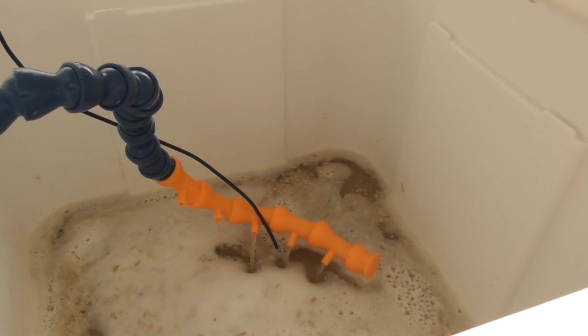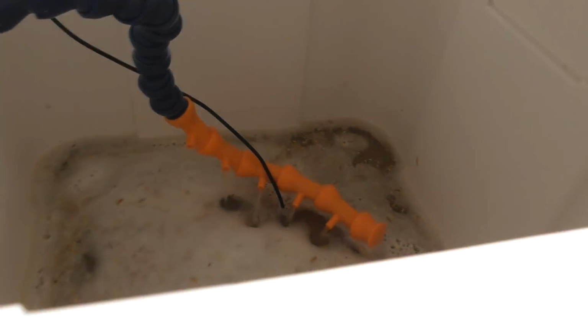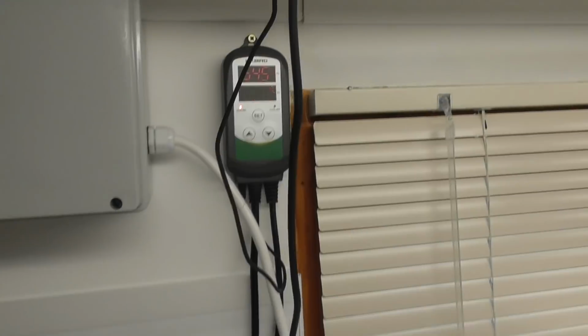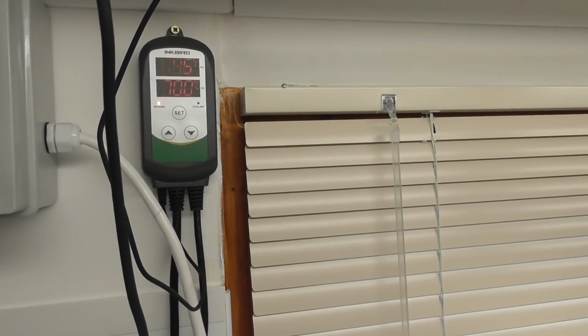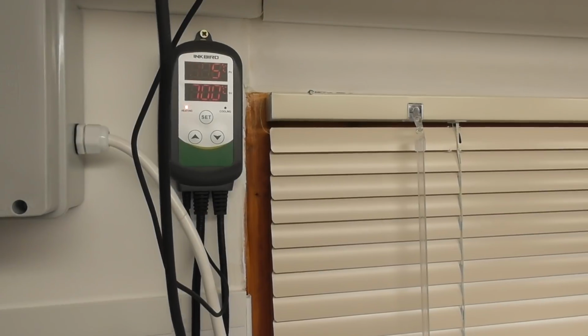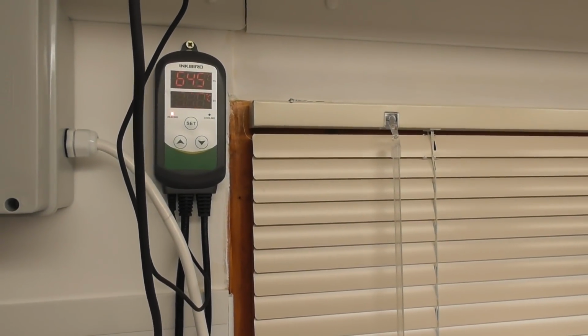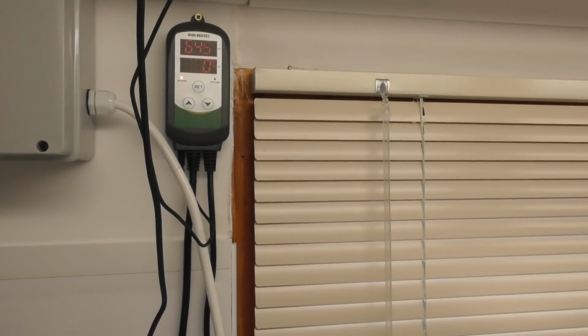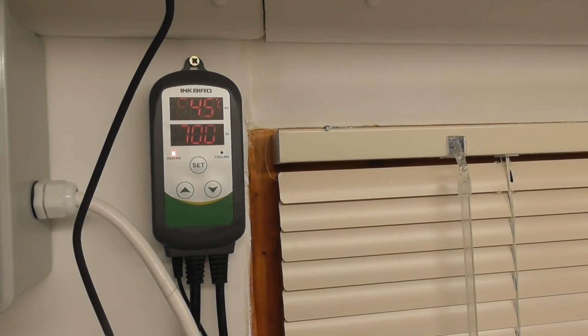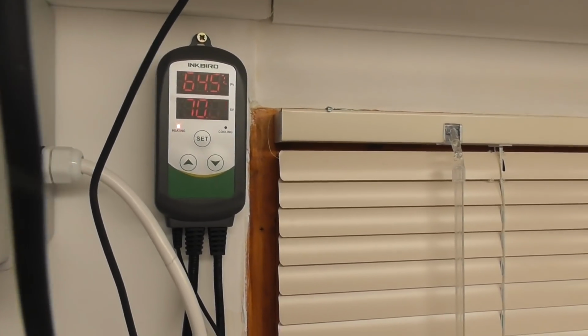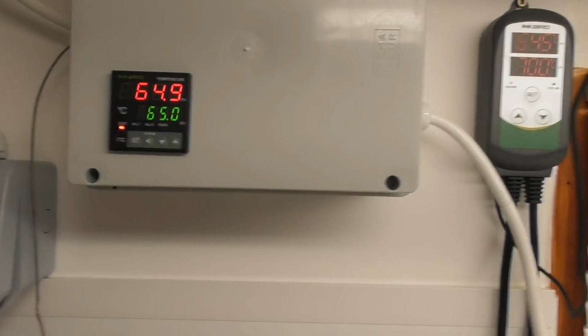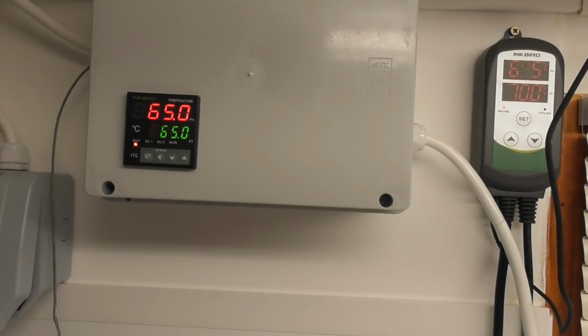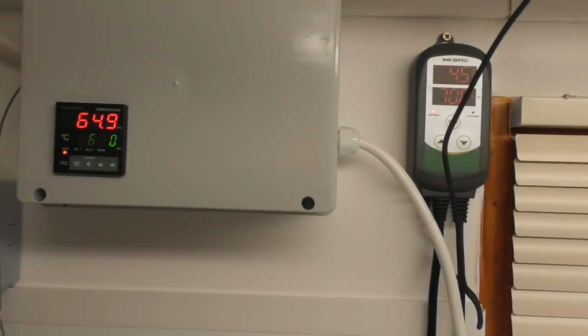That's recirculating nicely. You'll also see I have this other probe in there, coming from my Inkbird, doing nothing other than measuring the temperature, just as a secondary check. Not that I don't have faith in this thing, but generally they're always within range. That's at 64.5, that's at 64.9, so that's fine. Happy as a pig in shit with that. That's going, so okay.